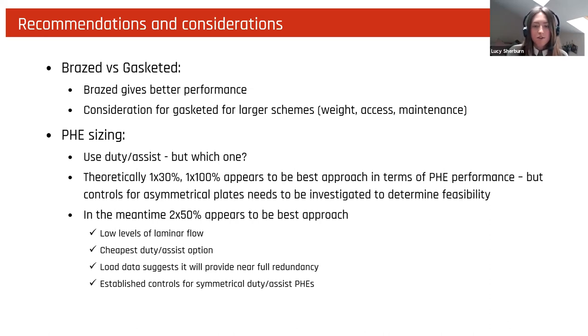So in the meantime, using two plates sized at 50% appears to be the best approach, so the duty assist at 2 by 50. This provided you with pretty low levels of laminar flow. It was ever so slightly the cheapest duty assist option. The load data suggests it will provide near enough full redundancy, and we have established control methods for symmetrical duty assist plate heat exchangers. Should note that this is quite high level and there are many project specifics that you should consider when choosing your plate sizes and what type of plate.